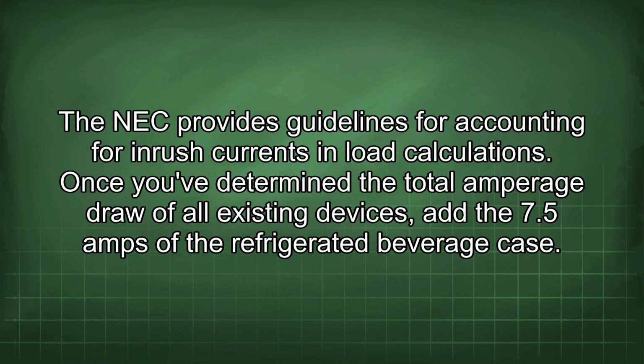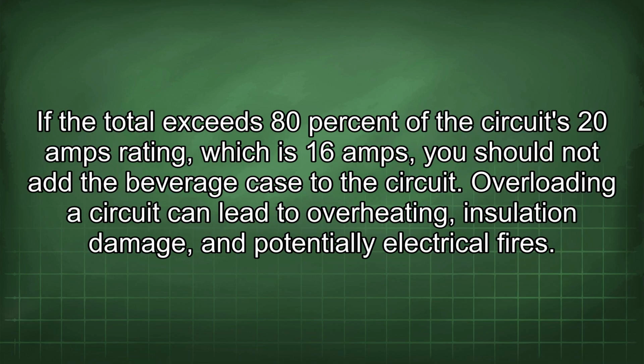Once you've determined the total amperage draw of all existing devices, add the 7.5 amps of the refrigerated beverage case. If the total exceeds 80% of the circuit's 20 amp rating, which is 16 amps, you should not add the beverage case to the circuit. Overloading a circuit can lead to overheating, insulation damage, and potentially electrical fires.